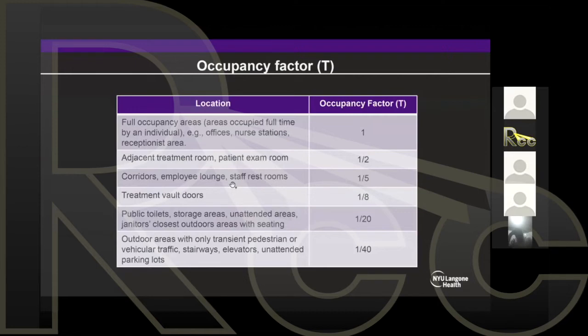The concept is the same. Is it the same occupant in the room? Is the room always occupied? So the factor will start to decrease, and these are the factors that you can use. For example, for the treatment vault doors, we reduce it to 1/8 because it's very rare that someone is right there at the door while all the treatments are being done. Someone could walk through the door, but it's reasonable to reduce the factor there. And you can see all the examples in NCRP 151.